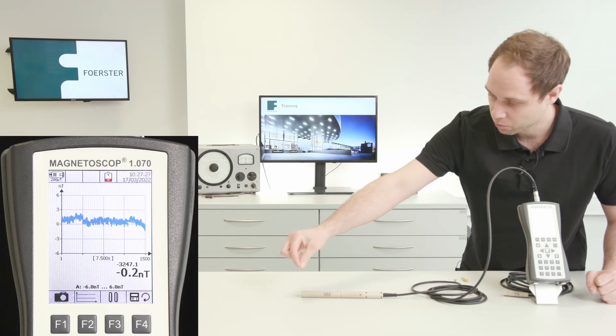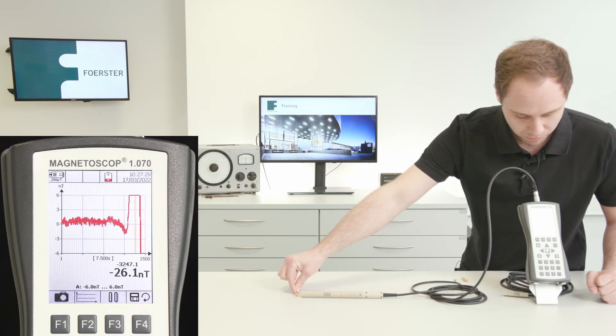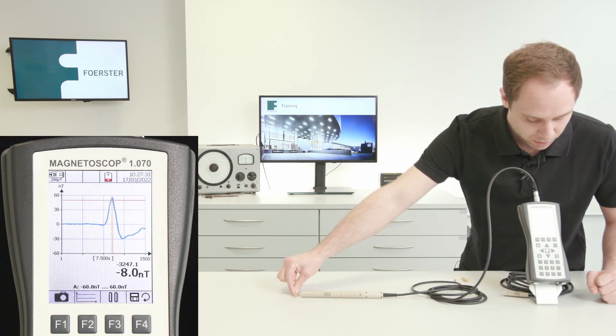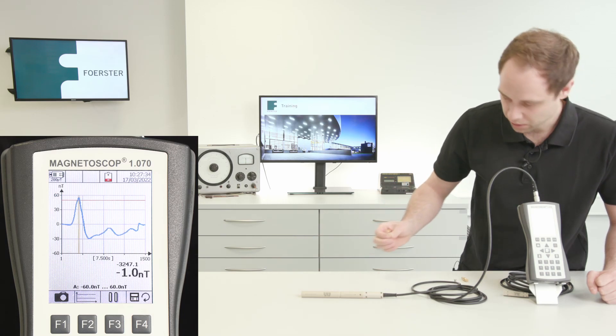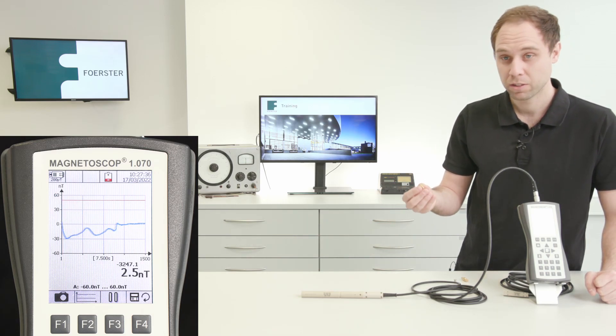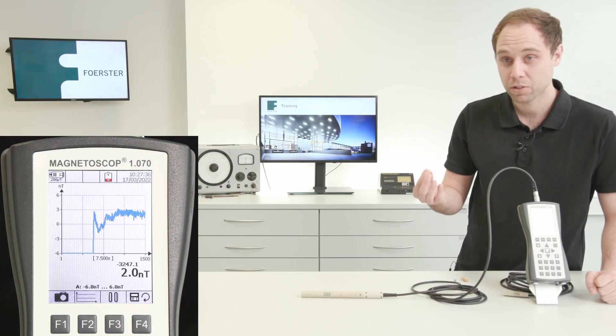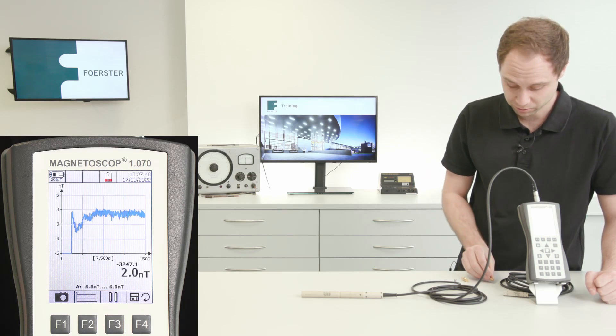Now I can move this part in front of the probe. We see this part causes 22 nanoteslas, so there's a small residual field. This component cannot be used in an MRI system.